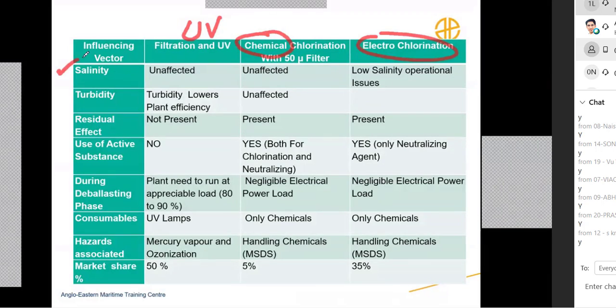Now salinity, will the salinity affect ultraviolet? No, it will not affect. So salinity is not applicable in UV, so it is passing. Turbidity, does it affect UV? Yes, it does. However, the other will pass in this case. Turbidity will not affect chlorination in any sort. So chlorination will still work in turbid water.